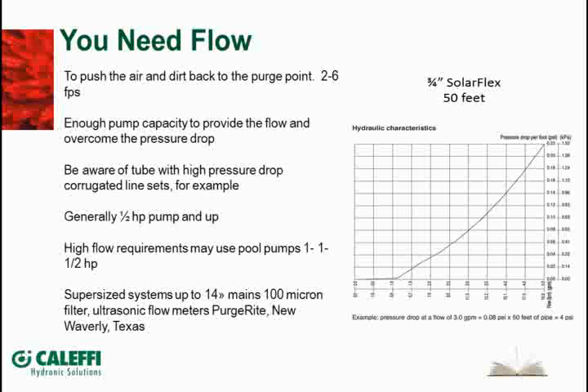All right, now if we're talking about getting the air out of the system, you need flow to get air out of the system. So to push air back to the point where you're going to purge it out, either out of the manifold on a little ball valve with a hose, or out of your air elimination device, your central air separator, you're going to need to be between 2 and 6 feet per second. Now that's the velocity of the fluid going through the pipe.